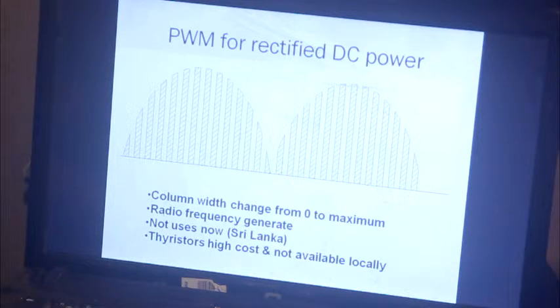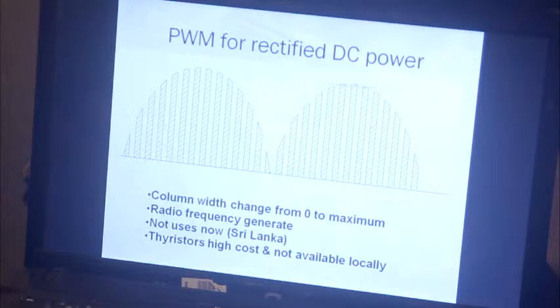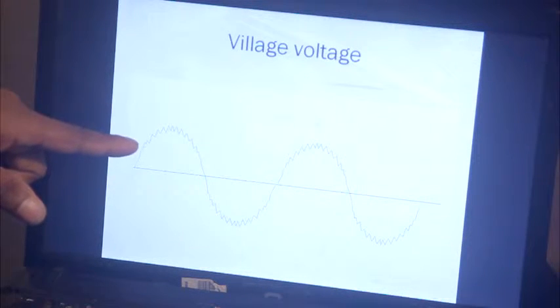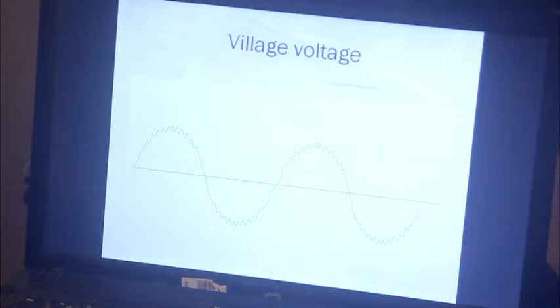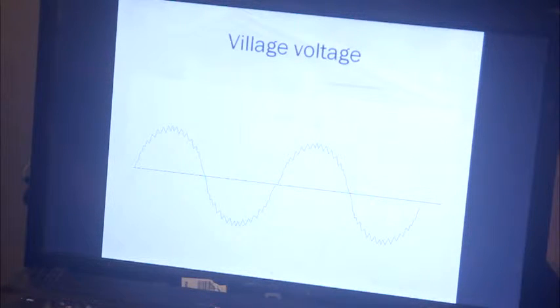One disadvantage of the mark space controller is very high frequency waveform chopping, which generates radio frequencies. The waveform going to the village shows the sine wave superimposed with very high frequency waves due to pulse width modulation. This distortion seriously affects the hydropower controller components. According to developers, electronic components burnt out during lightning periods, with a maximum lifetime of less than three months. Due to so many faults so quickly, this technology was abandoned and I have not seen this technology used in Sri Lanka or India.